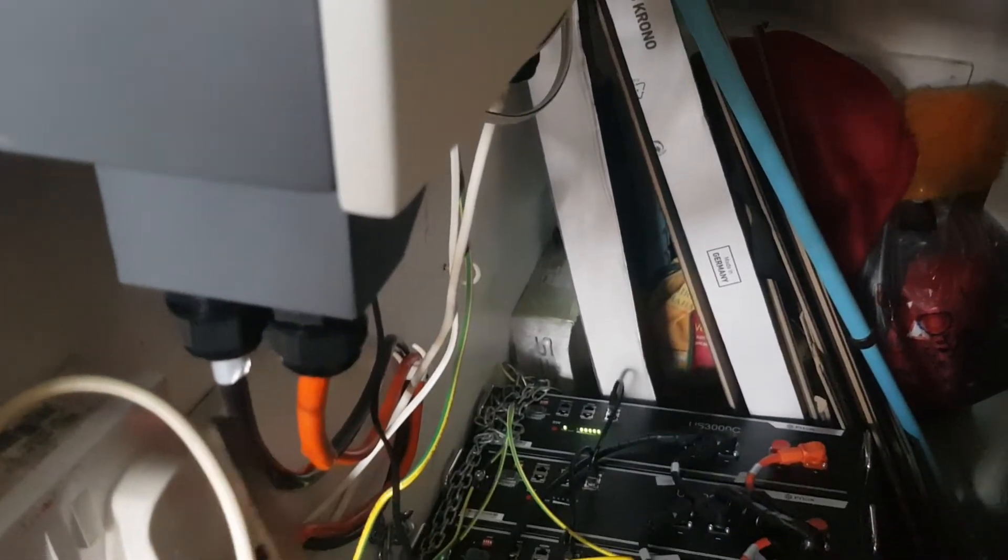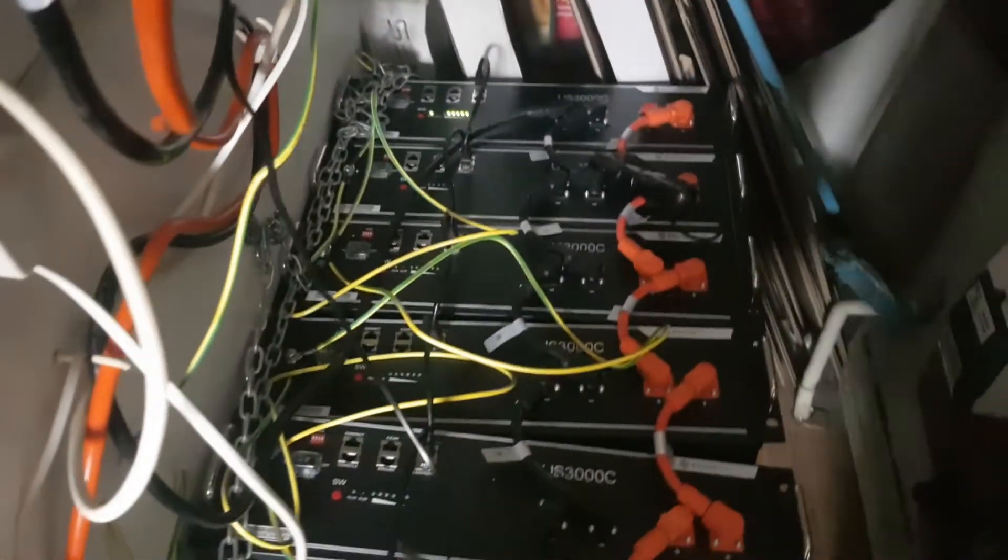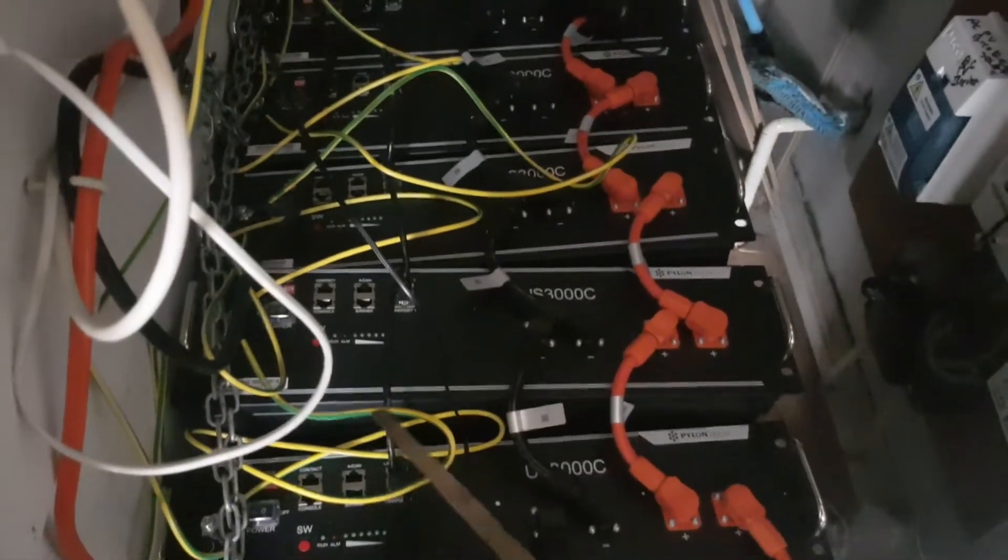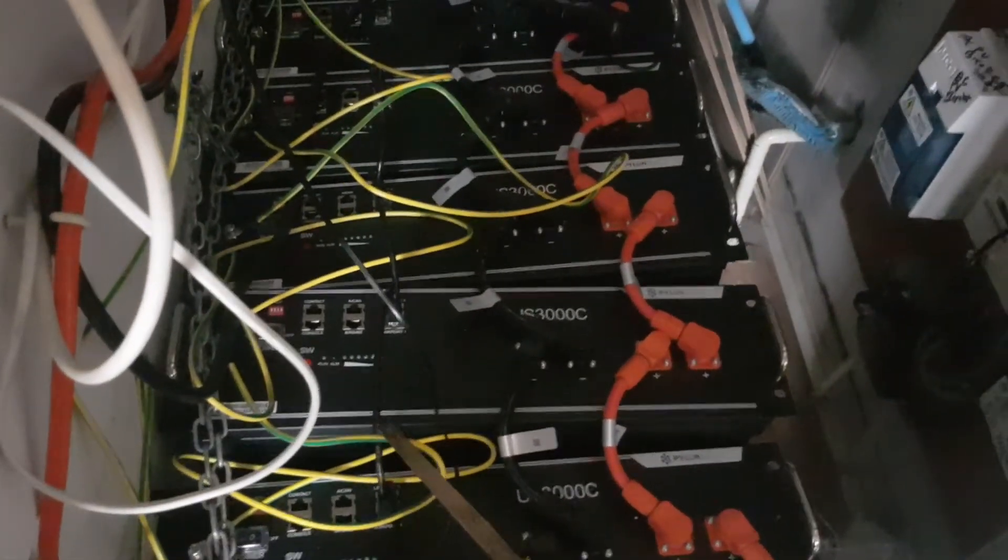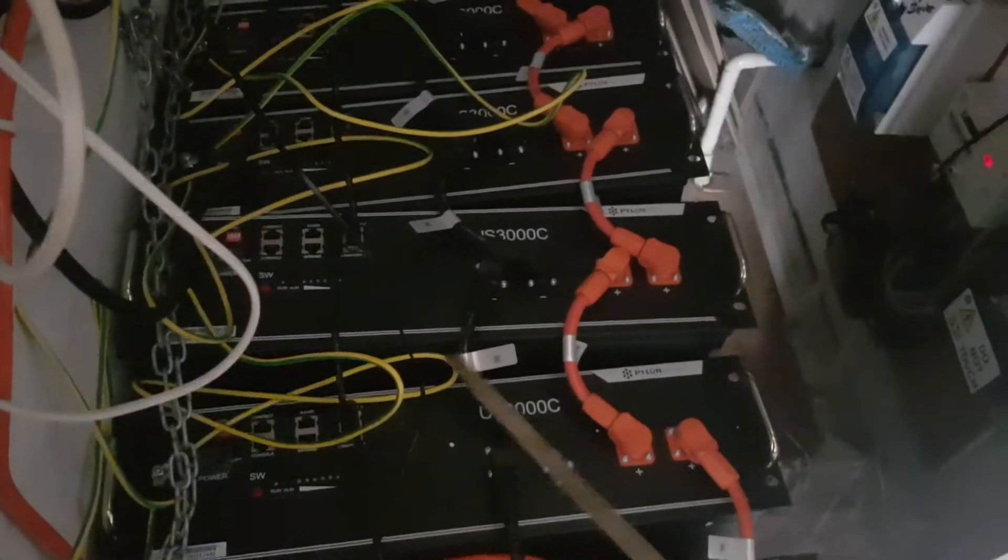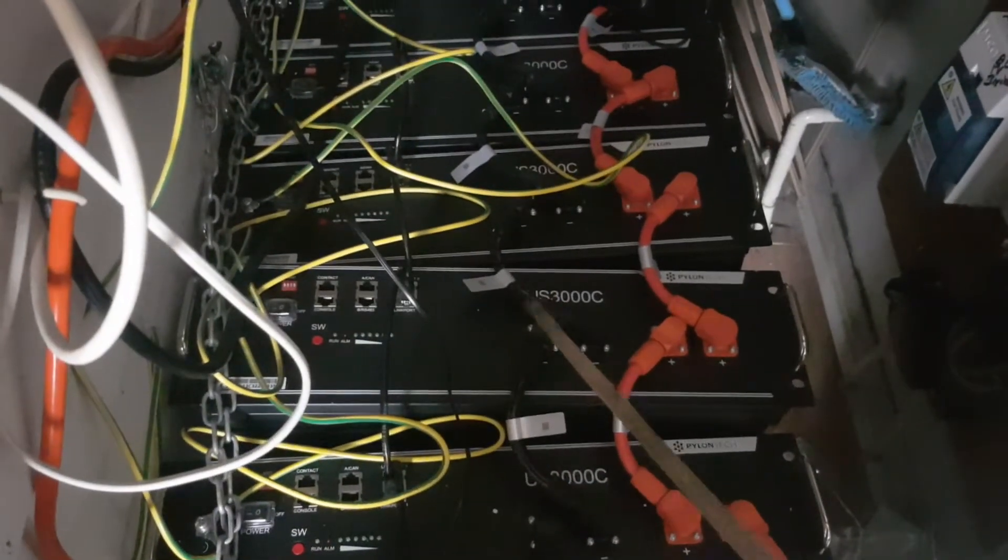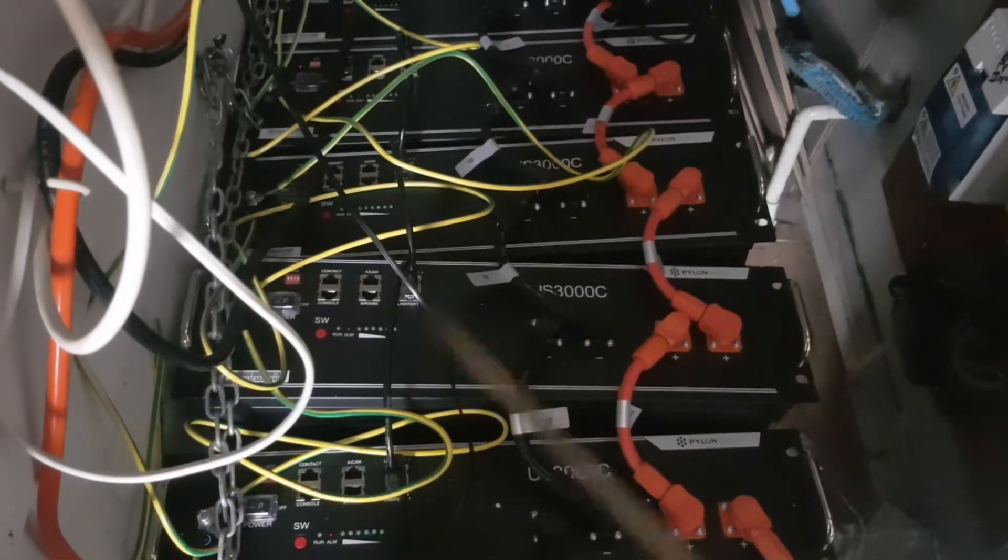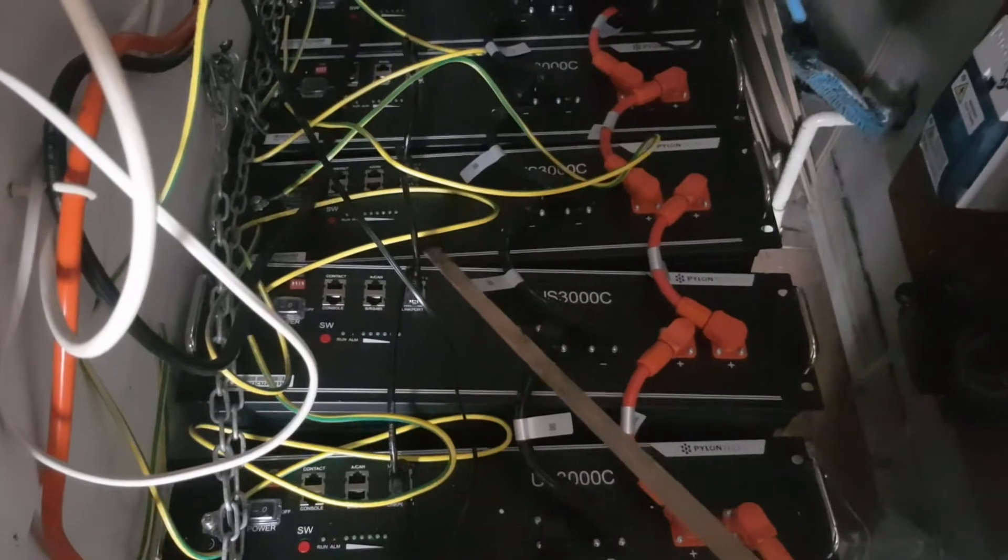Where you get a wiring fault within the inverter, you have to check all your negative and positive connections, your earth connections, and especially your BMS connection. Make sure they're all firmly plugged in because these things weigh quite a bit, and any knocking can actually upset these cables.